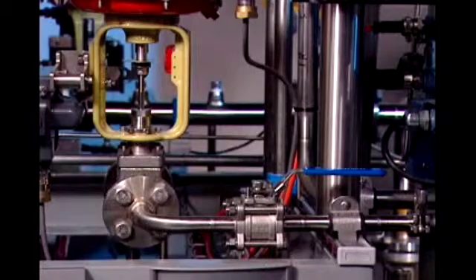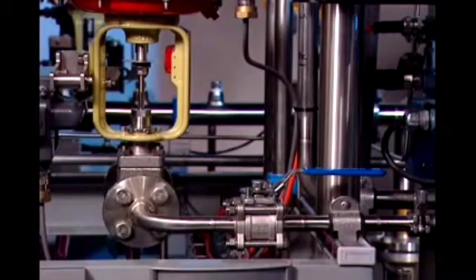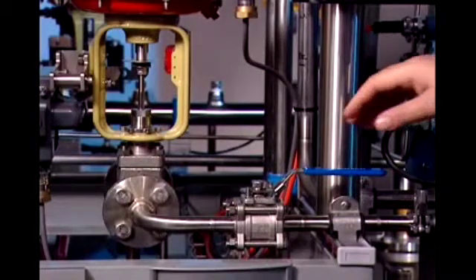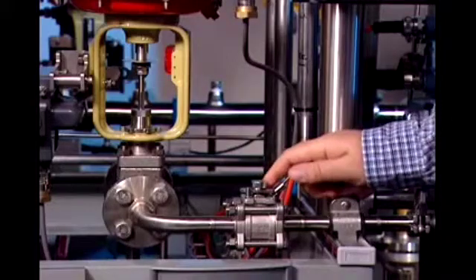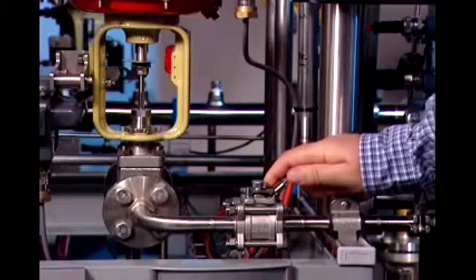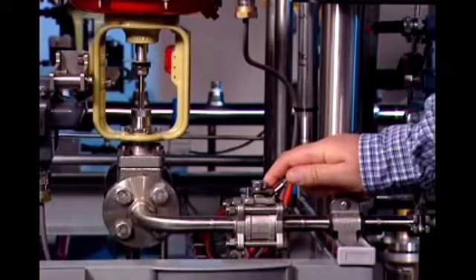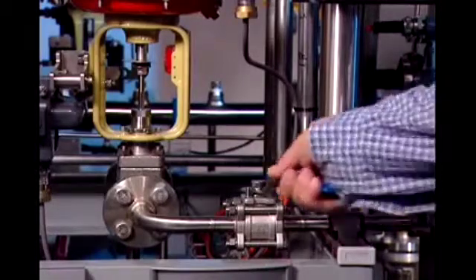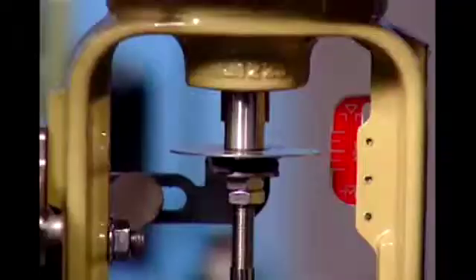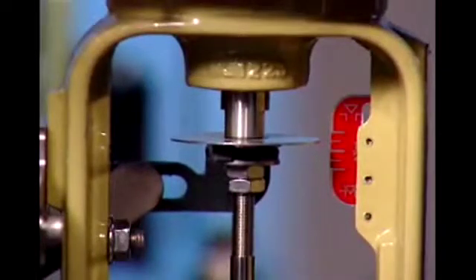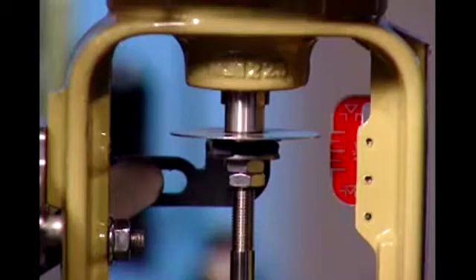Last, we're going to show the control in action in the field. I have a manual valve that I'm going to shut off, and we'll see the control valve opening up to compensate for the reduced flow. We can see the control valve opening up to compensate for the reduced flow.